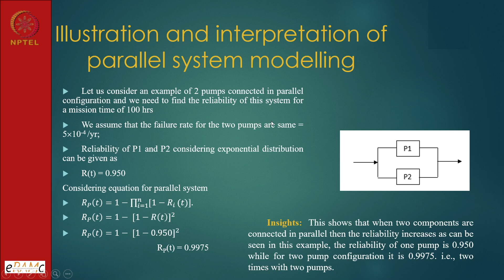So that means the estimate we got here is a very optimistic estimate. We have to consider common cause failure, which can fail both the pumps. Unless we take into account the impact of common cause failure, we will be giving, please note, most of the books give two parallel components and the reliability you estimate. No, that is not the way. Unless you factor in the common cause failure, you will not see the impact.